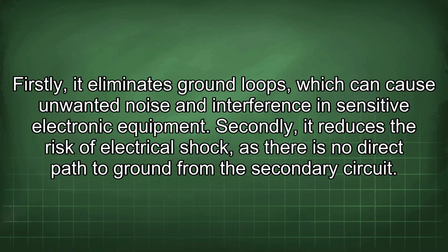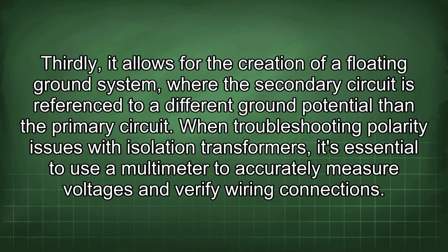Firstly, it eliminates ground loops, which can cause unwanted noise and interference in sensitive electronic equipment. Secondly, it reduces the risk of electrical shock, as there is no direct path to ground from the secondary circuit. Thirdly, it allows for the creation of a floating ground system, where the secondary circuit is referenced to a different ground potential than the primary circuit.